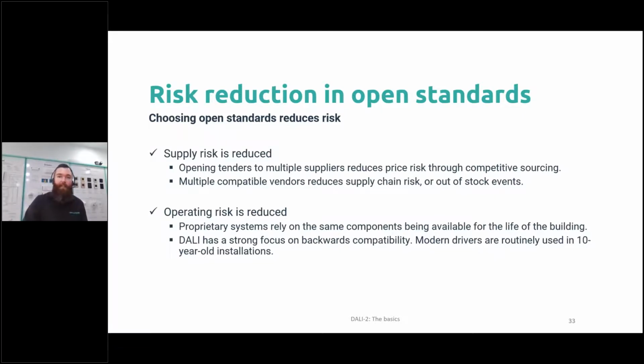If you need a specialty sensor that has, I don't know, ultrasonic or 30-meter detection radius, if you're on a proprietary system, you have the selection of the devices they make, and if they don't have one, well, you're out of luck, okay? Whereas in DALI 2, you can actually go out to the market and you can choose. There are manufacturers that specialize just in making those specialty devices. You can bring them into that system. You minimize the risk in your sourcing. The other one is actually component availability.